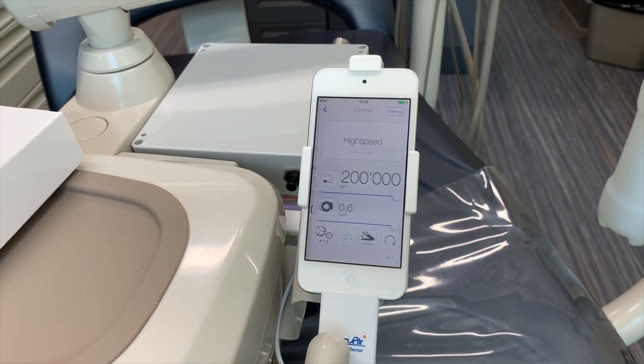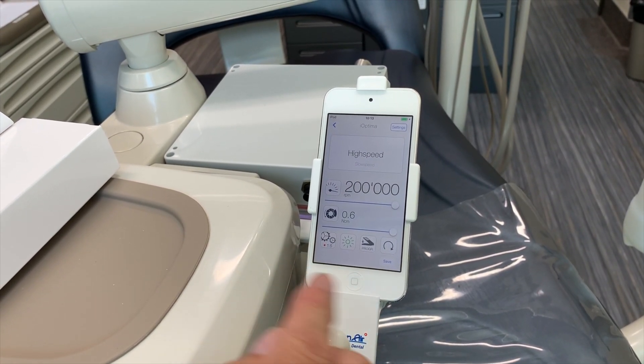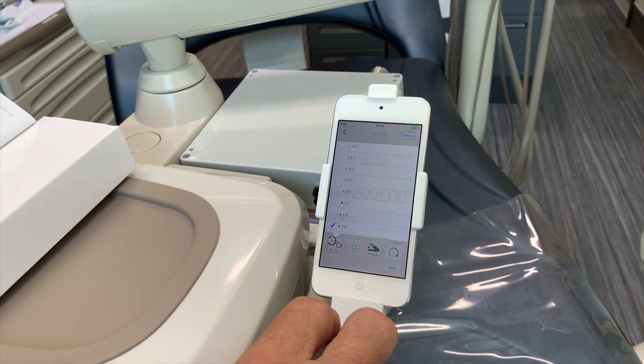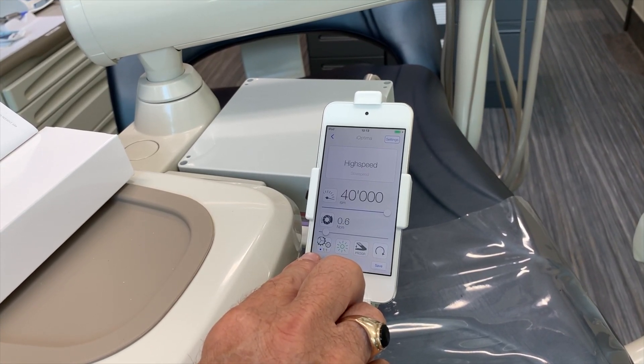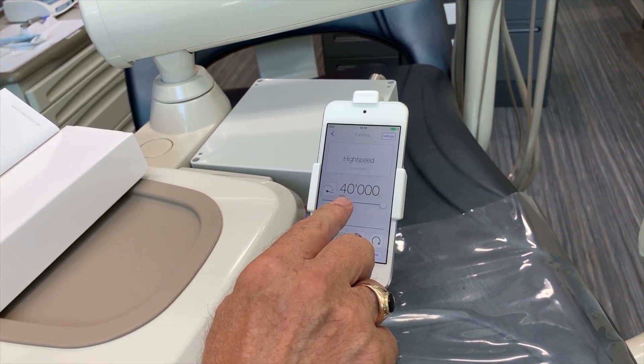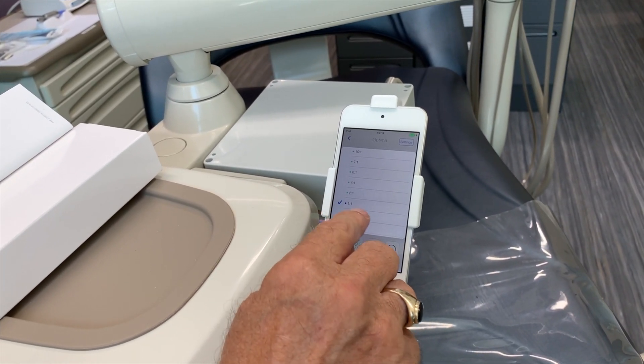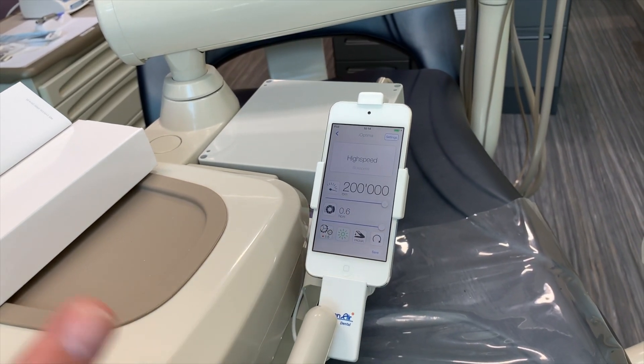Should you choose restorative dentistry, it's set up for high speed at 200,000 RPM. You can adjust the light intensity and change the contra-angle you're using — for example, a one-to-five ratio. If I change that to a one-to-one, you'll notice it changes to a blue dot showing gear ratio one-to-one, and it drops down to 40,000 RPM because it's no longer a one-to-five increasing speed. Going back to a one-to-five, it goes back up to 200,000 RPM — all done automatically.